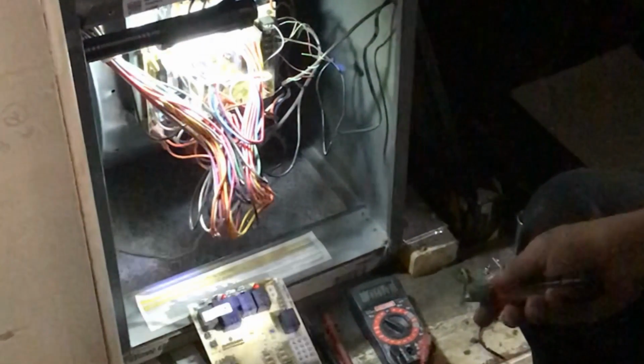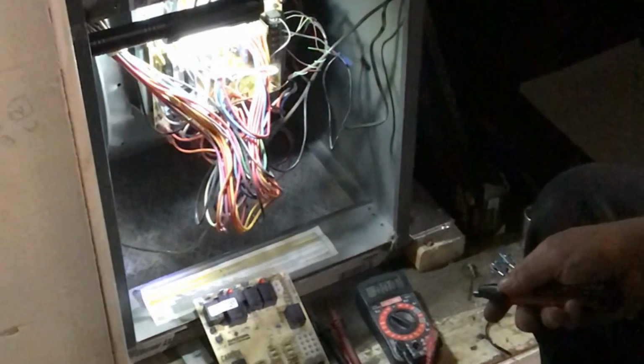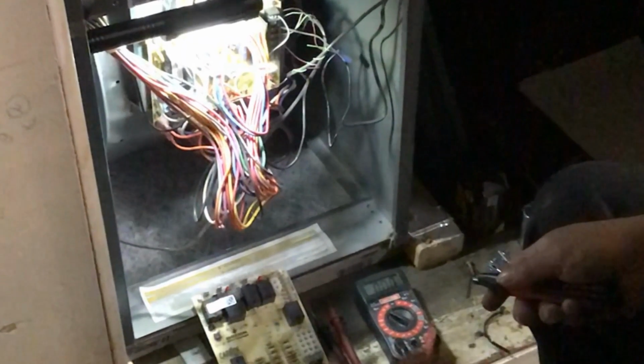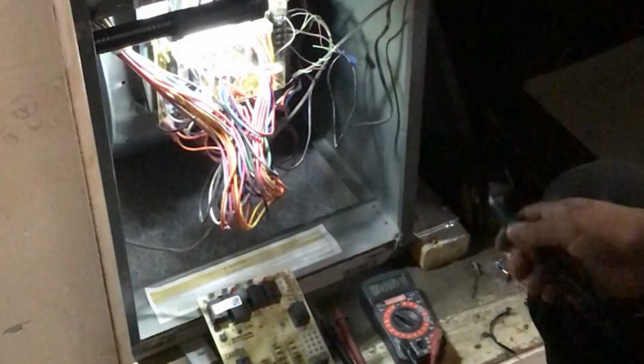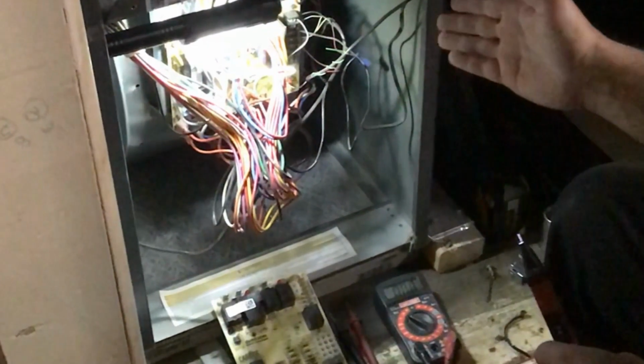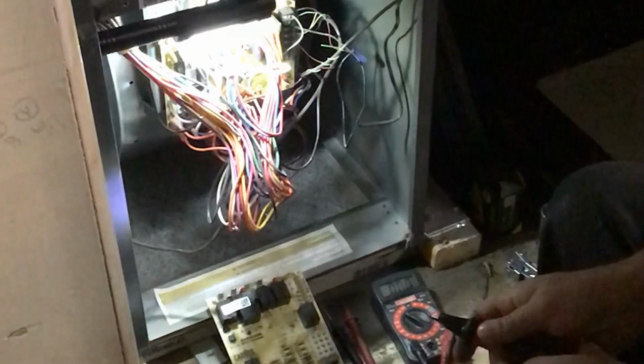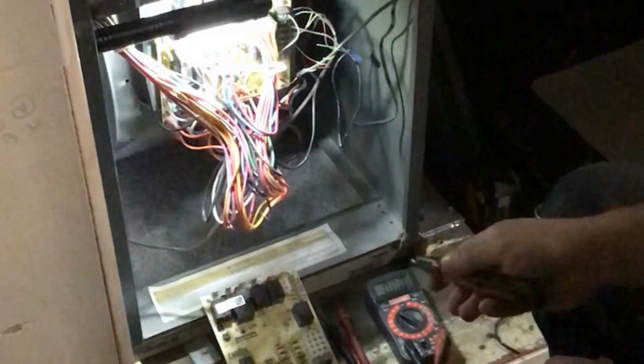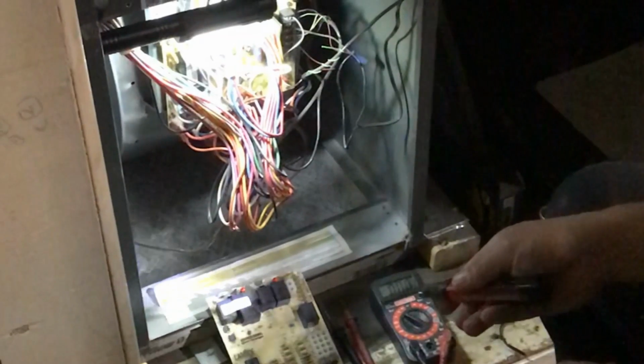Okay, so we've checked our circuit board. We're going to assume that we have power going out to the fan. We've replaced our capacitor, and we still don't have an operational fan. We're going to have to replace this blower motor. And I showed you earlier on the board how to check the output to the fan motor.